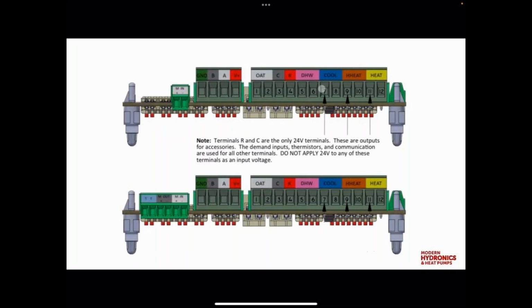We have a cool call, which is a fixed set point temperature. And then the DHW call here is actually where you would hook up a thermistor, so the touchscreen on the unit is the aquastat for the DHW. Then moving over, we have R and C, which is just 24 volts out of this unit. And we also have a place here for an outdoor air temperature sensor.